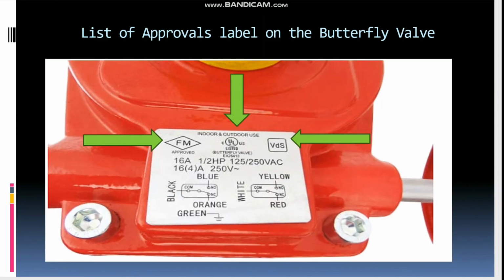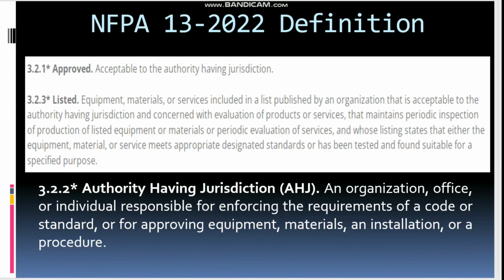Coming to the topic, on most of the firefighting materials you can see these types of listings like FM approved, UL listed, VDS or LPCB. So there will be different approvals. First you will see what NFPA is saying. Based on NFPA, approved means acceptable to the authority having jurisdiction.